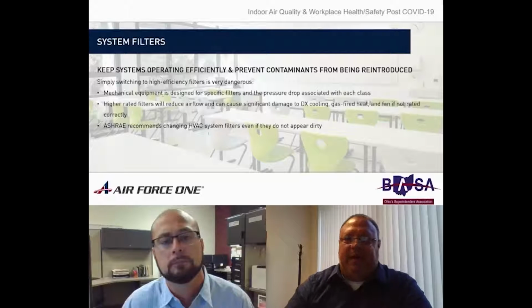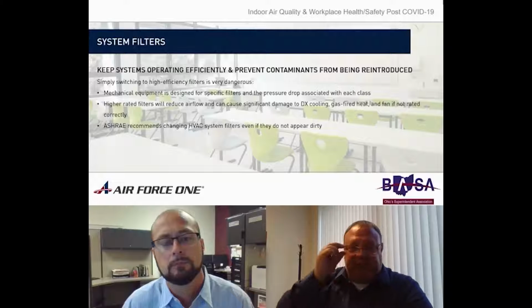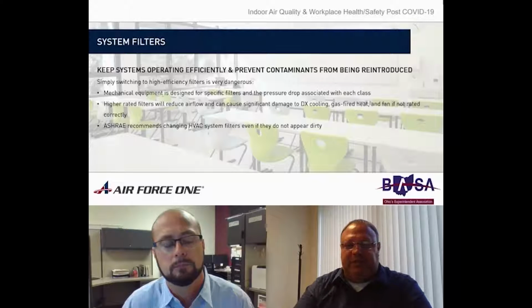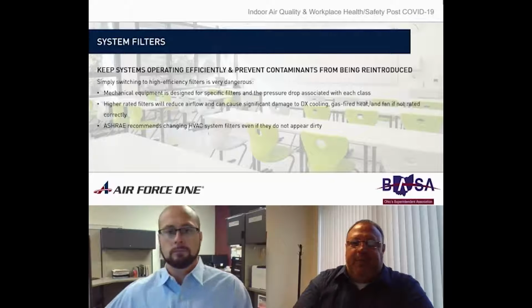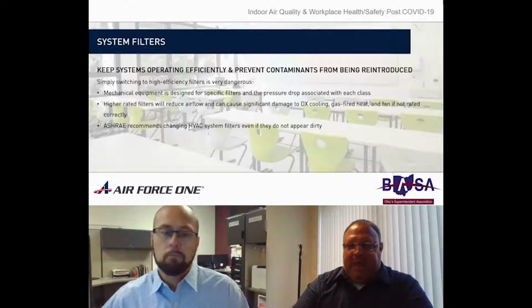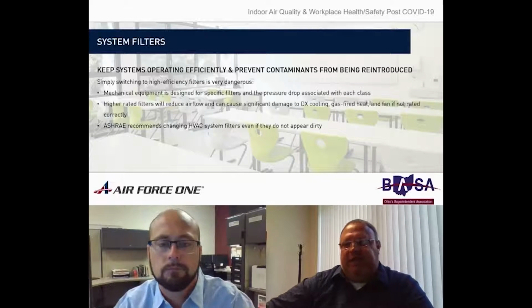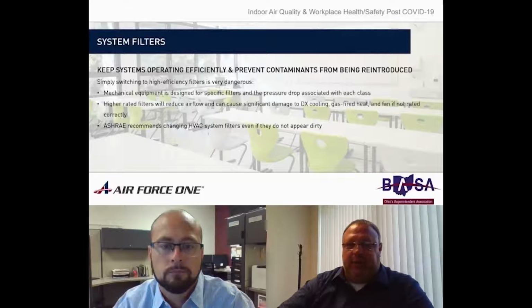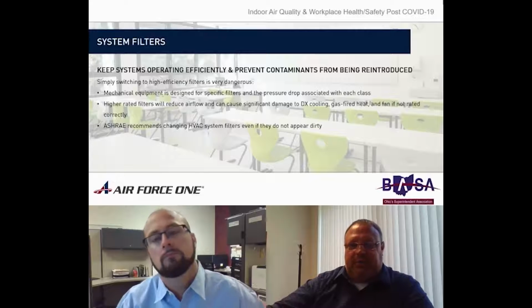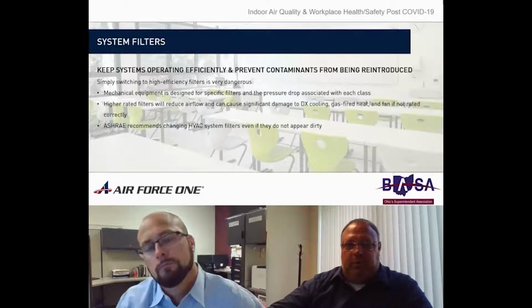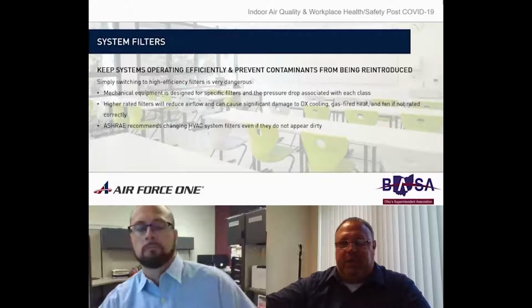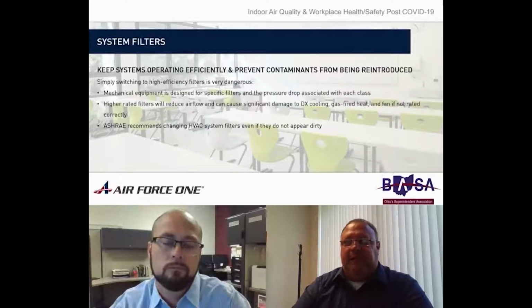Right. So I'd like to add to that, Austin, specifically with some of the requirements set by the state of Ohio and the CDC. Most equipment is designed for MERV 8 filters. That's the standard. And moving to anything that has a higher filtering capability reduces airflow, as Austin said. Specifically MERV 13 and then HEPA. At that point in time, when you move to those filters, the pressure drops can sometimes be double to 3 times, and then as you move to HEPAs, it could be 4 or 5 times that of a MERV 8.